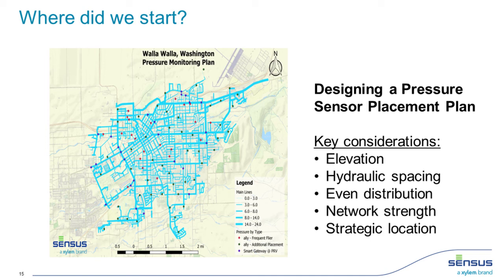I wish we had the graph here that showed where the break happened and what we saw with the hourly resolution. It happened the day before, and that's where Joe started looking to say, hey, something's going on here. By the next morning, it had surfaced. It probably came in on the hourly, every 4 hours, so you're gonna get 4 data points in the first 4 hours of that leak. We saw it, we just weren't sure what to do with it at that stage, but it was big enough that it blew the road up the very next morning.